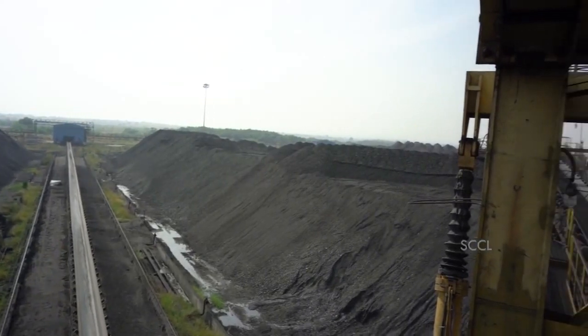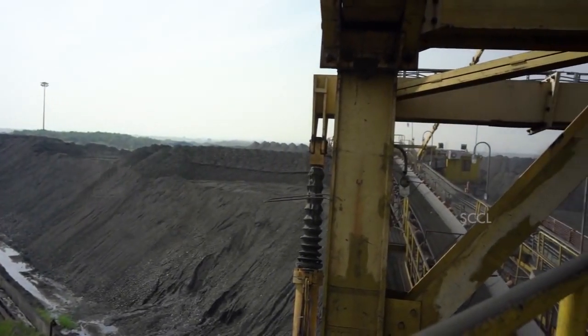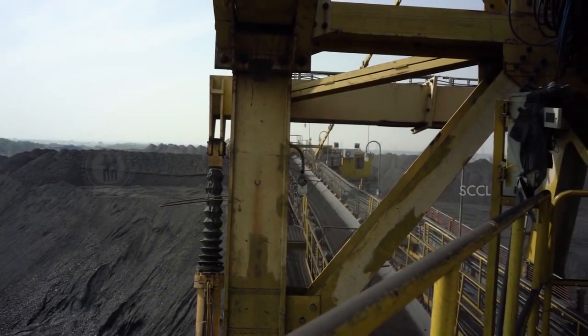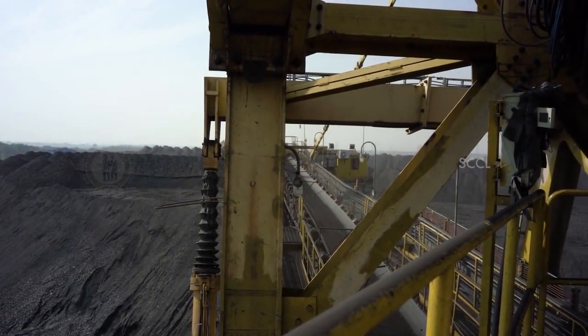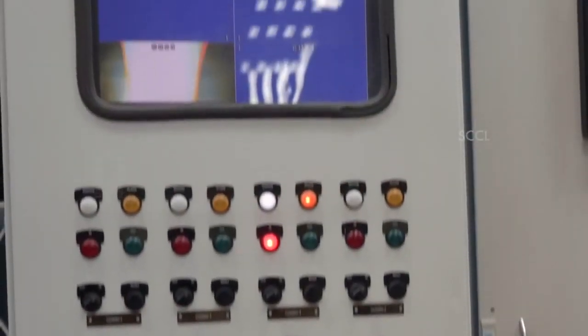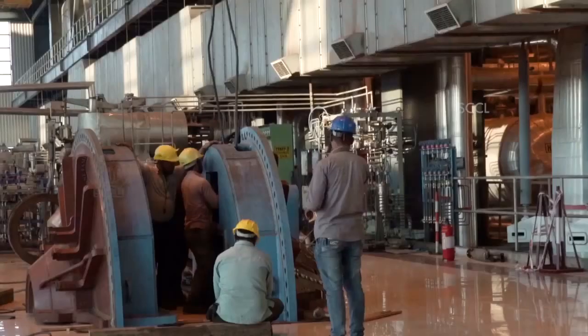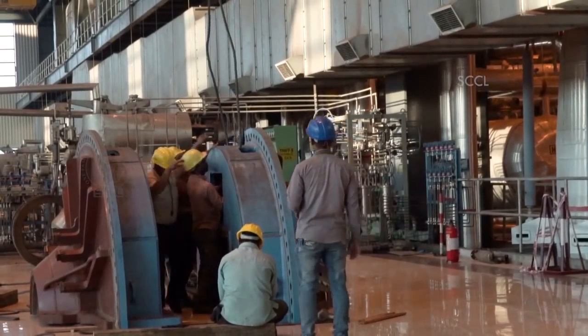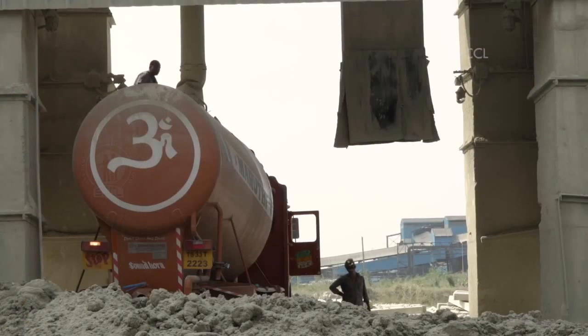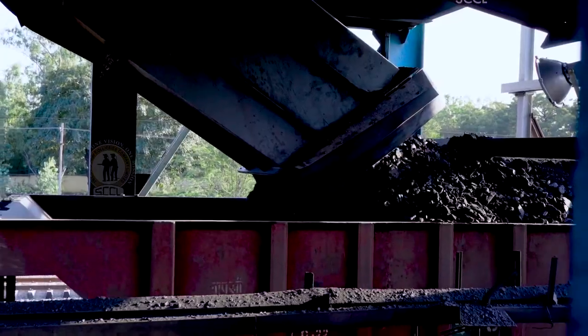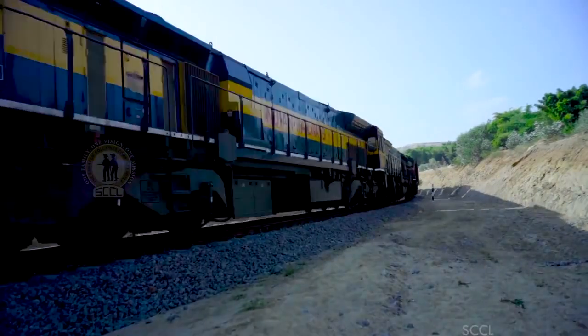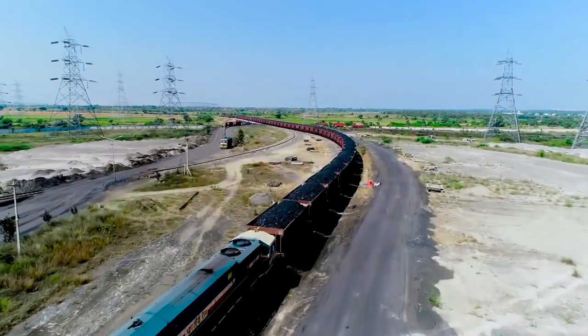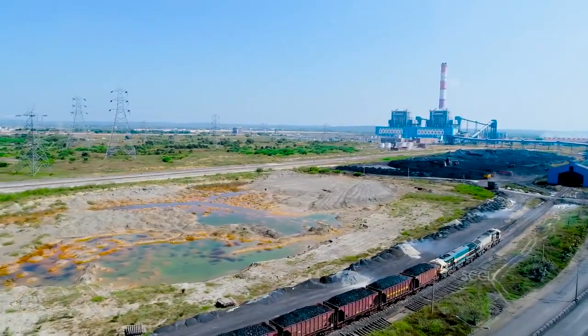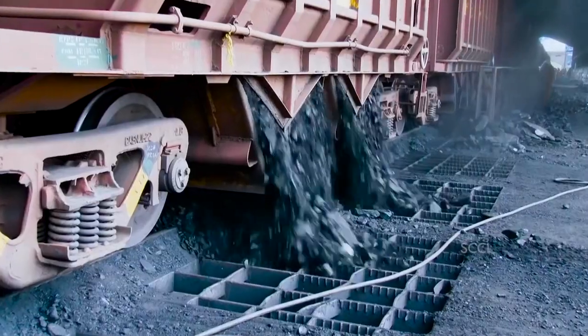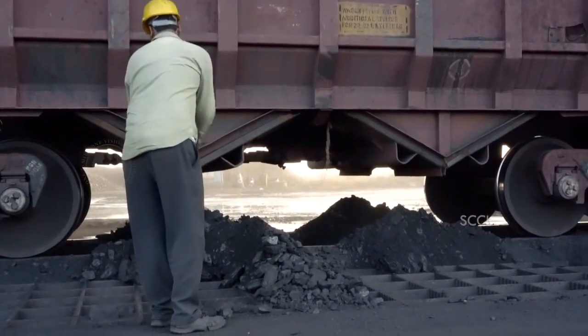STPP needs coal of G11 grade with 4,200 GCV with ash content of about 30%. If the coal is of lesser quality, more coal needs to be burned to produce the rated power, which increases the cost of production as well as ash percentage, which further creates problems in ash evacuation. Coal from mines is transported to the plant by a coal rake, which is loaded at coal handling plant at Srirampur. A 21-kilometer track has been built by SCCL for transporting the coal to the power plant.